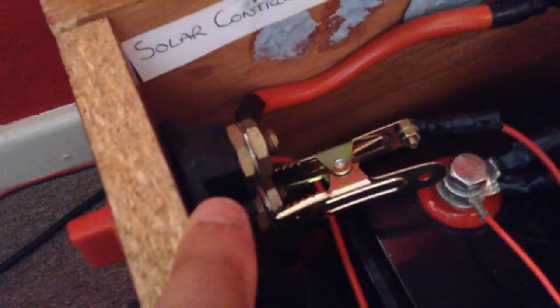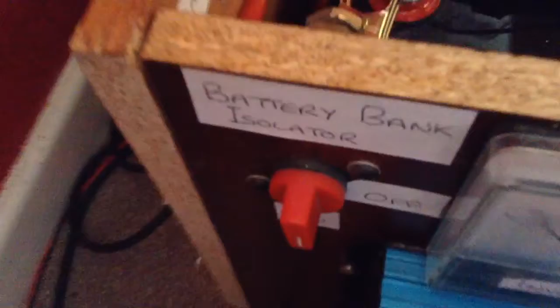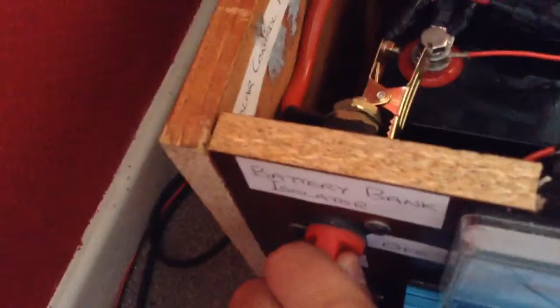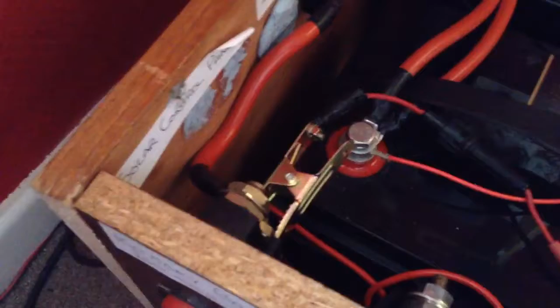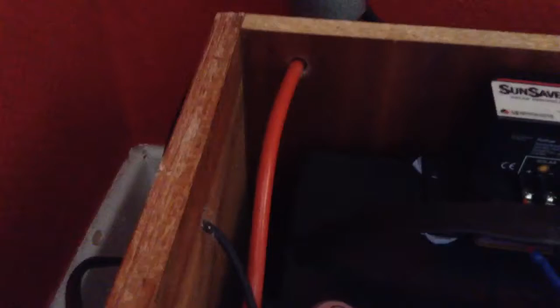From the fuse we go to another important thing, a main disconnect switch, the battery disconnect switch, here. This battery bank isolating switch cuts off everything from the batteries. If there's any emergency or technical problem, just switch off here and the batteries are disconnected. A safety thing again. Then the main cable goes down, comes out over there, and goes up to the charge controller.